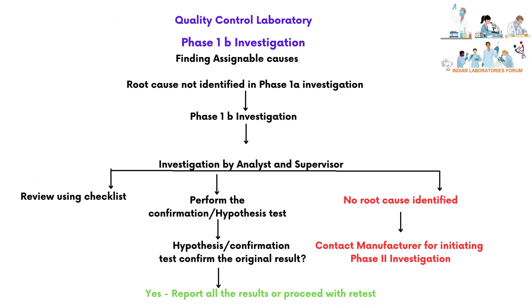Phase 1b investigation will be done to find out the assignable cause, and will be performed by the analyst and supervisor of the laboratory. The laboratory supervisor should review the test data using a predefined checklist and perform the confirmation or hypothesis test based on the probable root cause. If the hypothesis or confirmation test confirms the original result, report all the results or proceed with retest. If no root cause is identified in Phase 1b, proceed with Phase 2 investigation.